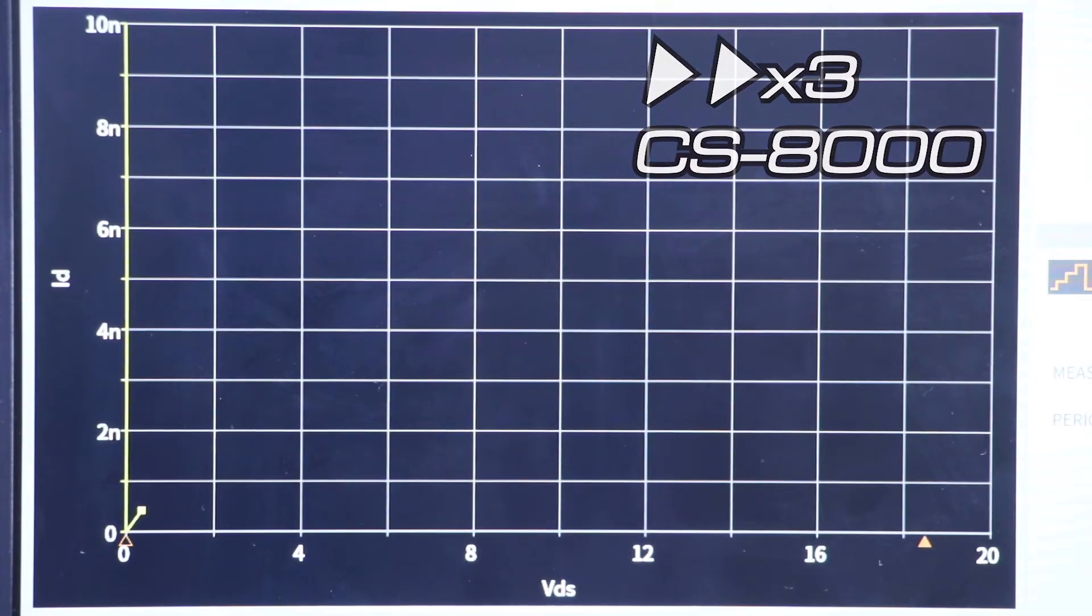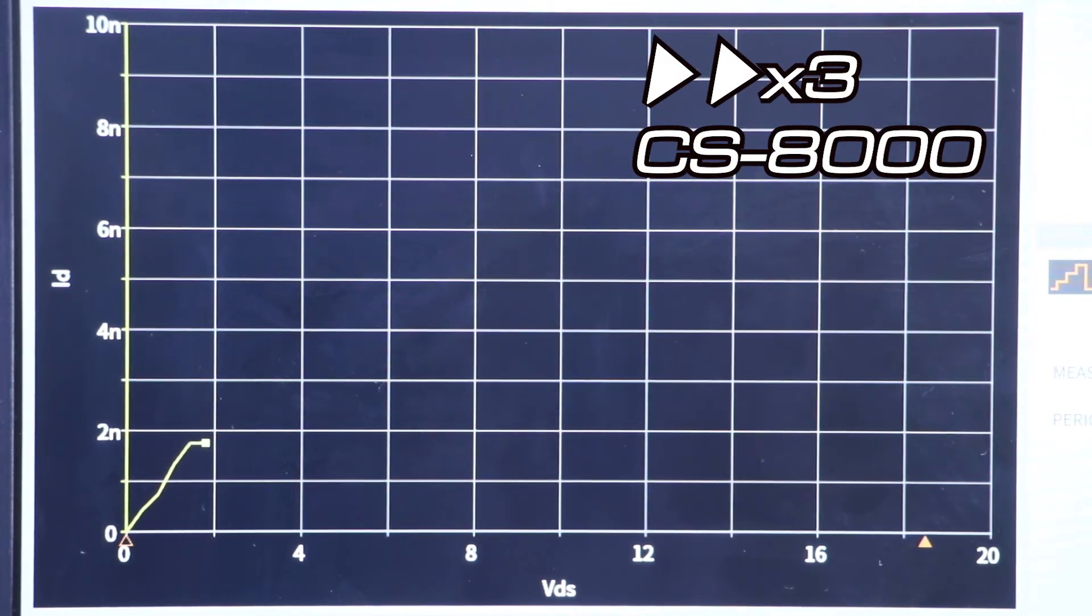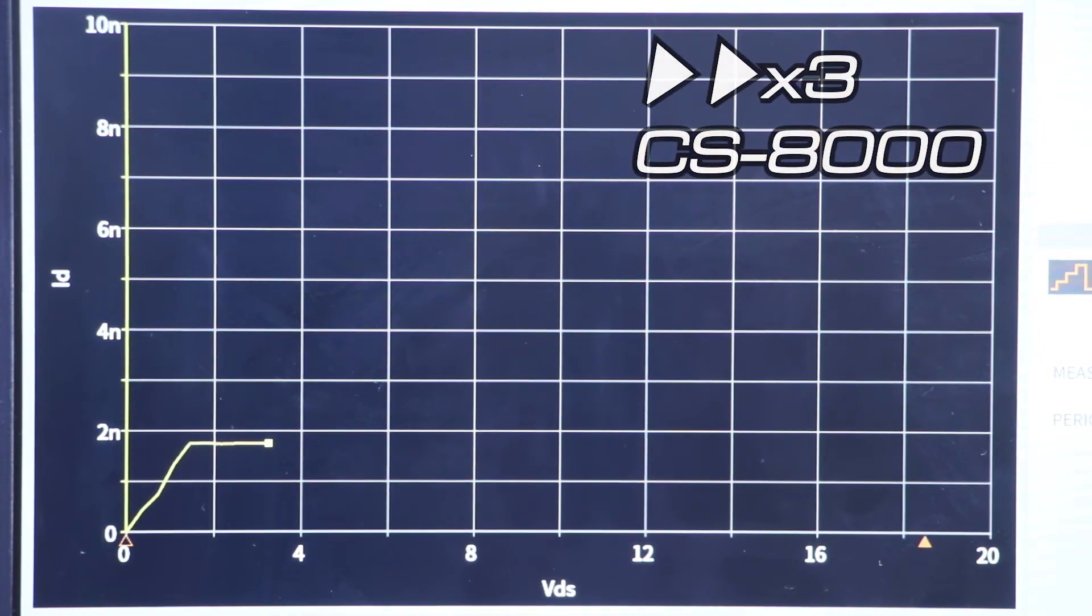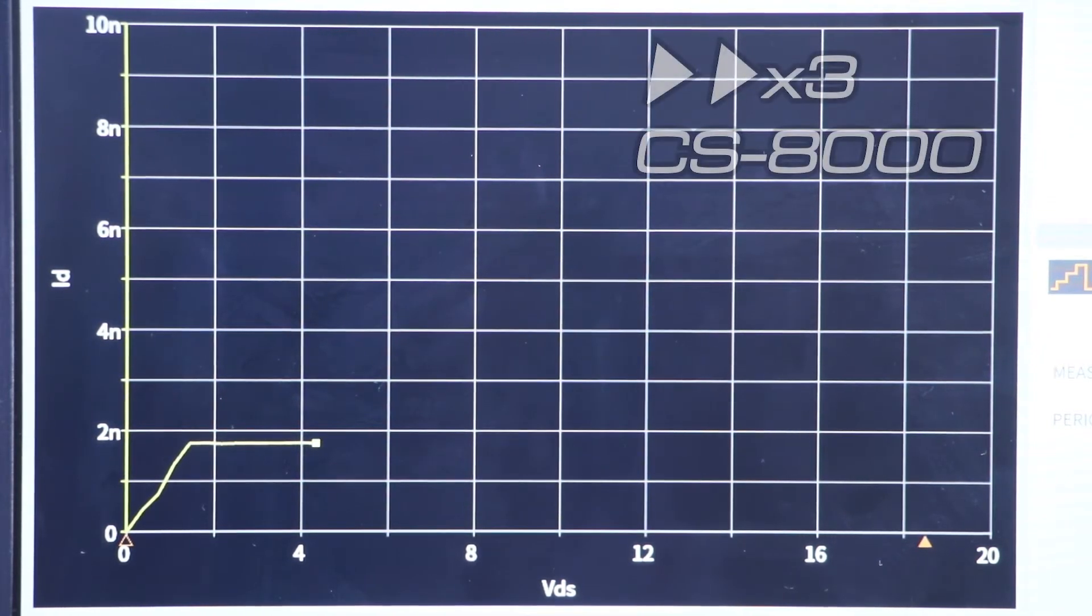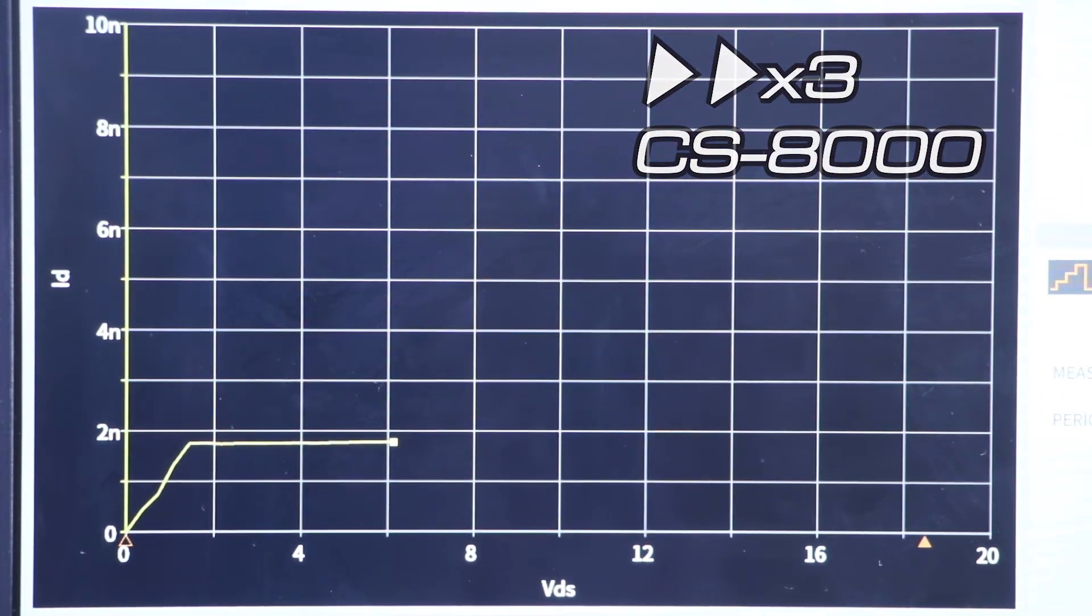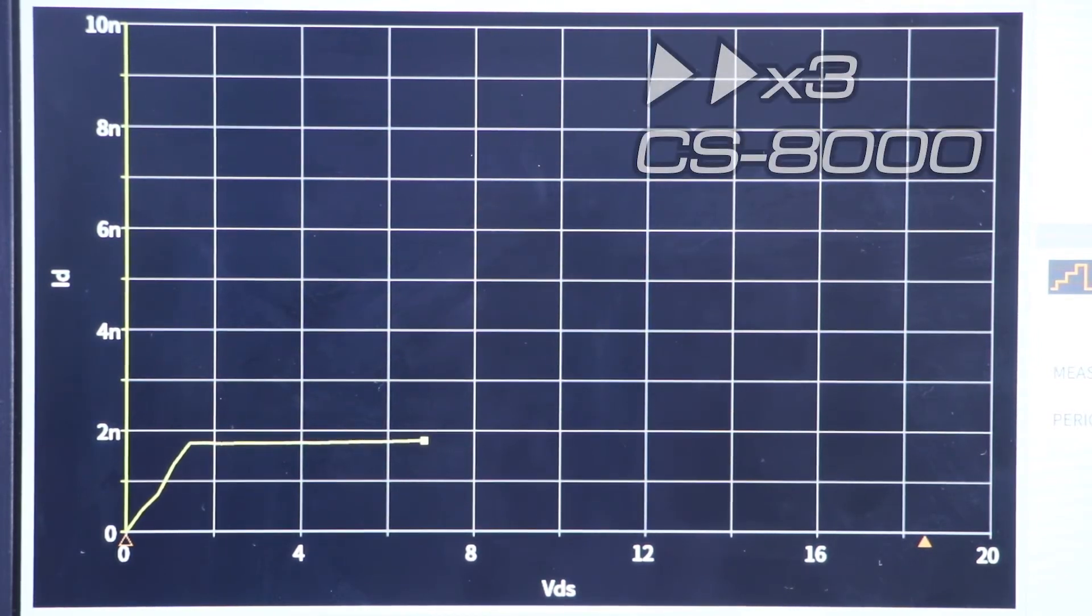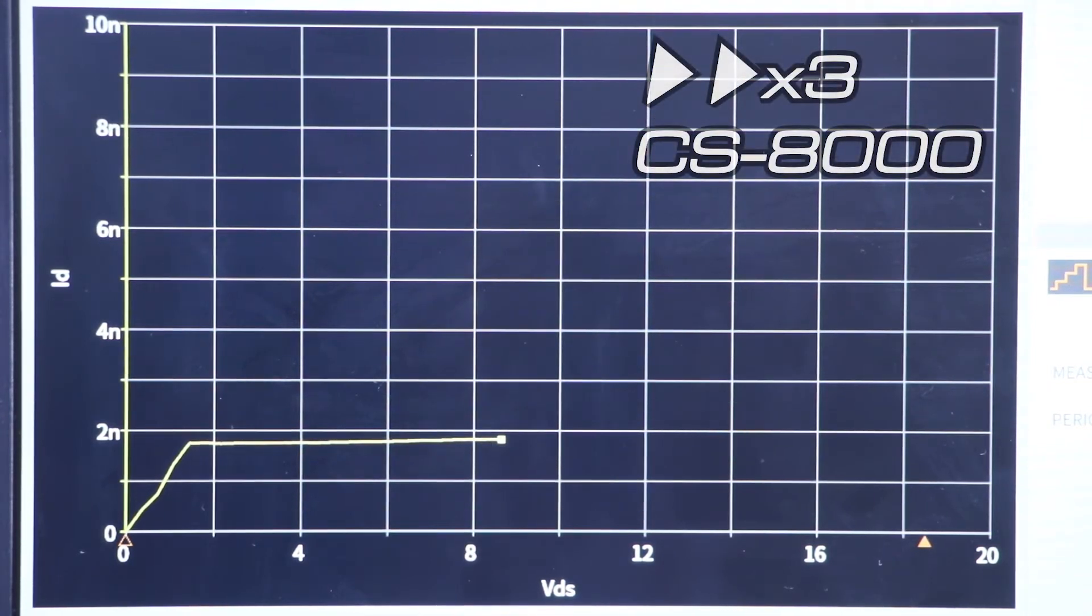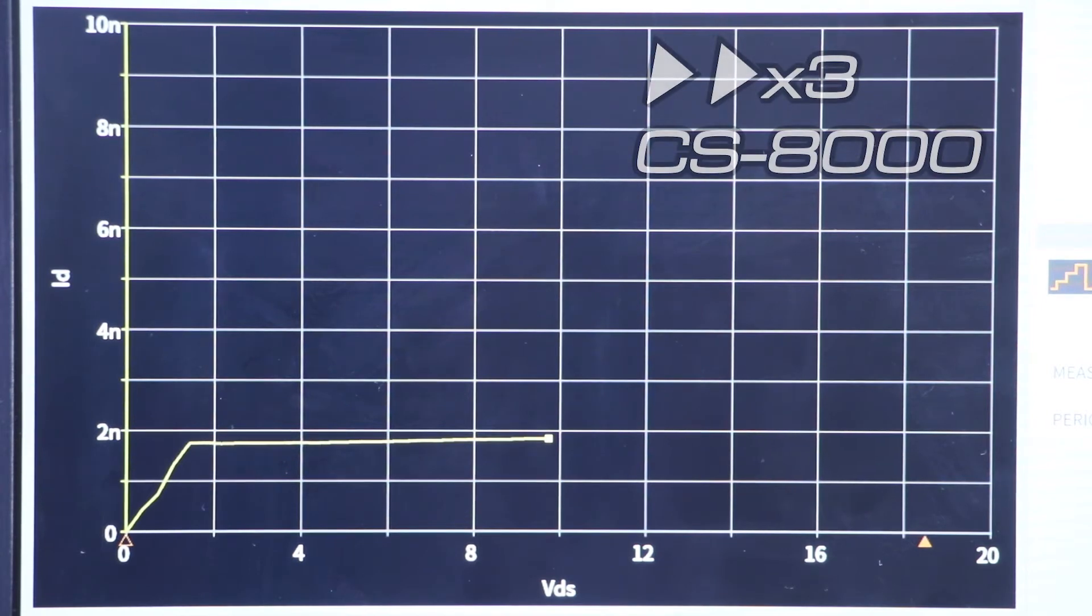Next, let's try CS8000. We use main unit CS8200, HC unit CS220, and the test fixture CS322 HV-HC for this demo. The sample is the same as the last one. Power MOSFET from STMicroelectronics. It is measuring leakage current.